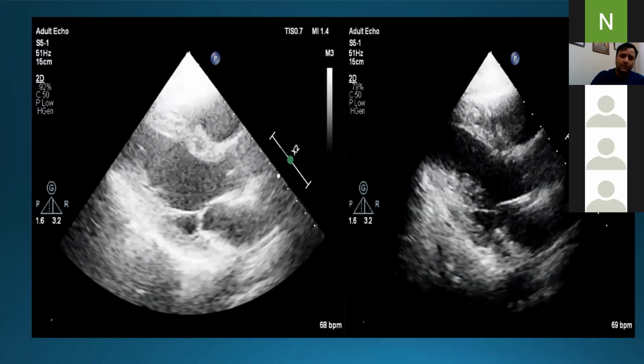In black and white TVs also, when we increase the gain, the overall picture becomes brighter. So let's remember, gain is brightness. When we increase the gain, the overall brightness increases. So gain should be around 50. It should be around 50, as is the compression. If you don't understand the physics of it, I'll tell you what to remember. At least a frame rate of around 30 to 40, I told you. Gain around 50. Another one is compression, around 50.